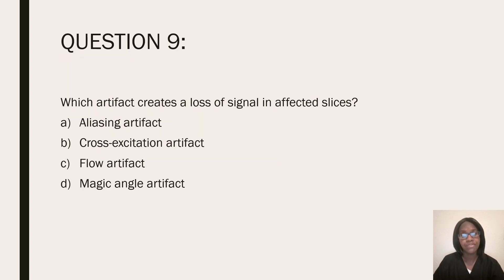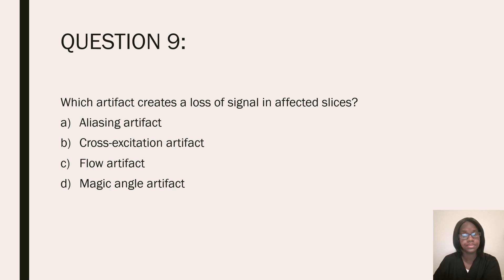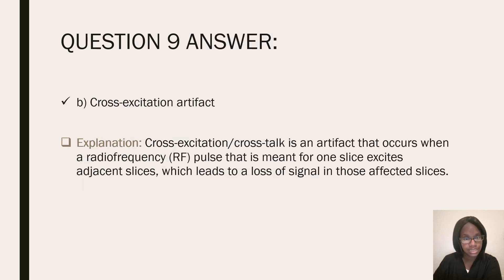Question nine: which artifact creates a loss of signal in affected slices? Aliasing artifact, cross excitation artifact, flow artifact, or magic angle artifact? Cross excitation artifact — also known as crosstalk. This is an artifact that occurs when a radio frequency or RF pulse that is meant for one slice excites adjacent slices, which can lead to a loss of signal in those affected slices.